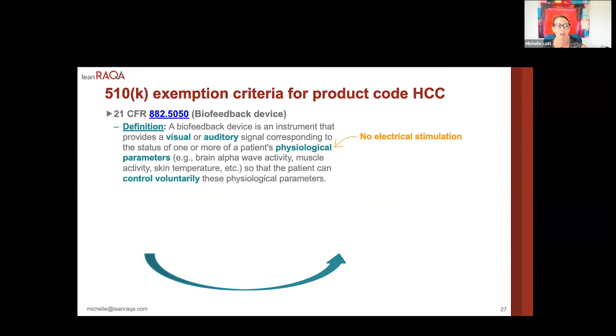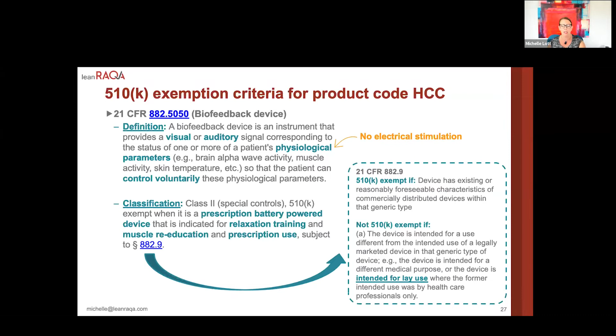And so the reason why it's important to understand all these nuances is that it's only 510K exempt when it is a prescription battery powered device for relaxation training, muscle re-education, and prescription use. So in that case, you can say it's 510K exempt. But if you say it's intended for lay use, you can see how it exceeds the description of this regulation for prescription use. And now you have to consider a 510K and possibly even a de novo, depending on your conversations with the FDA and your technology.